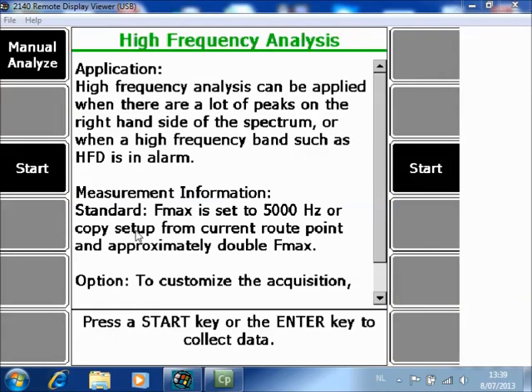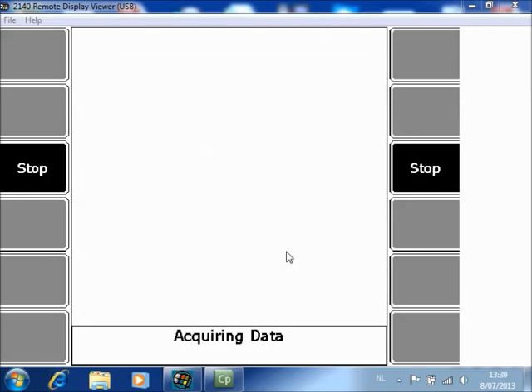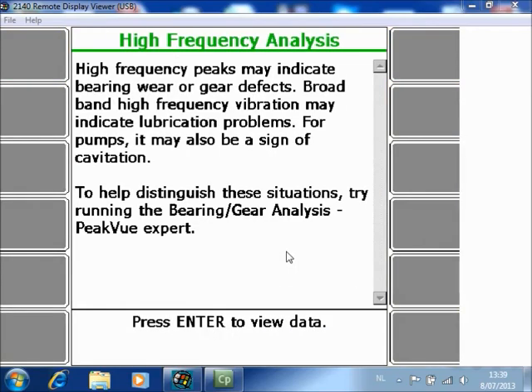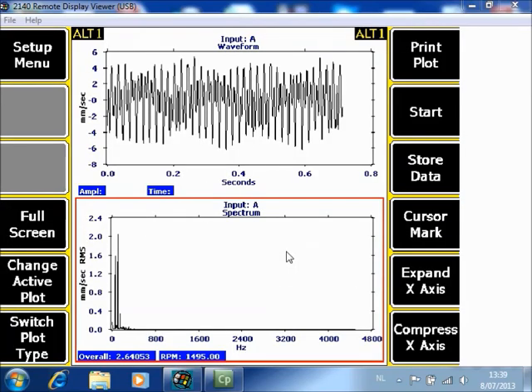An additional measurement will be collected with an Fmax that is approximately double. Push F3 start, then press Enter to review the data. As you can see, there is an additional spectrum and waveform measured with the double Fmax. If you now push F9 store data, it will be stored in the route mode with an additional tag for analyze data.